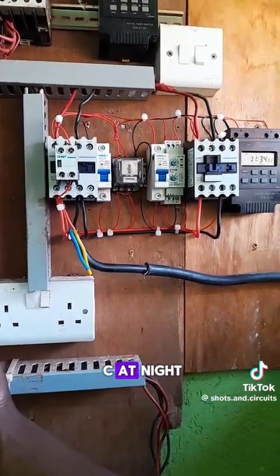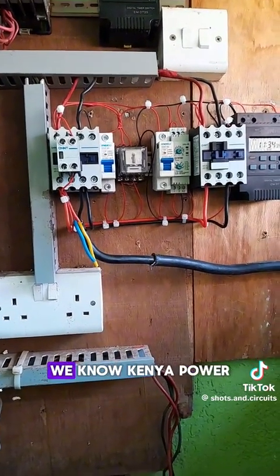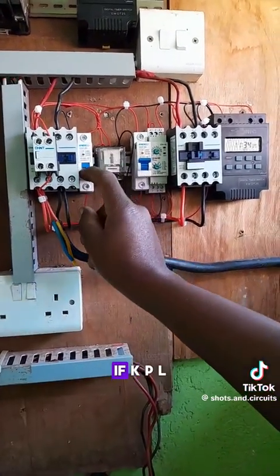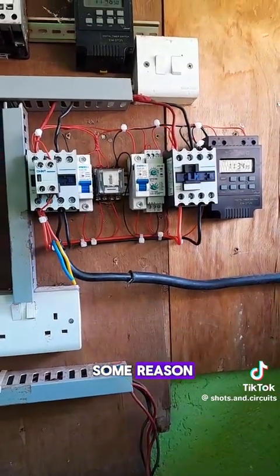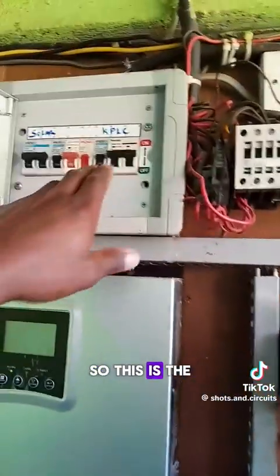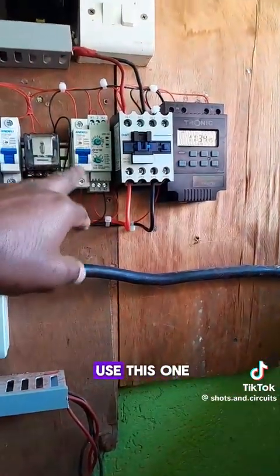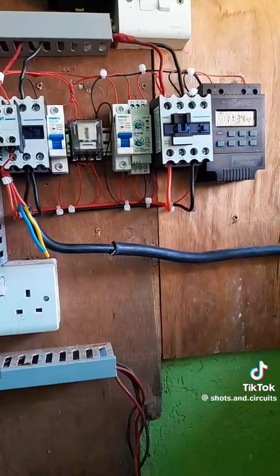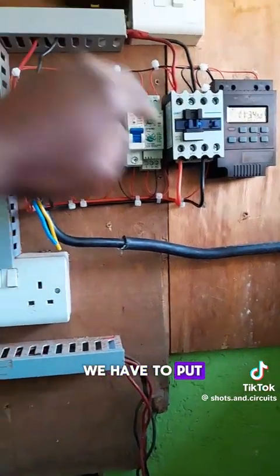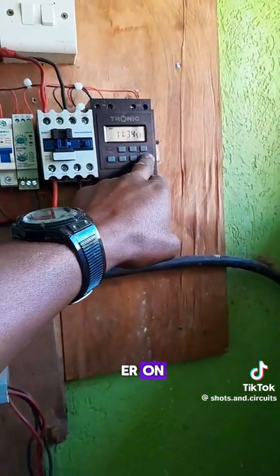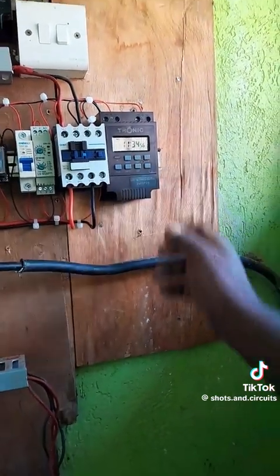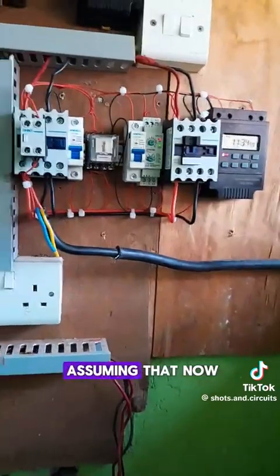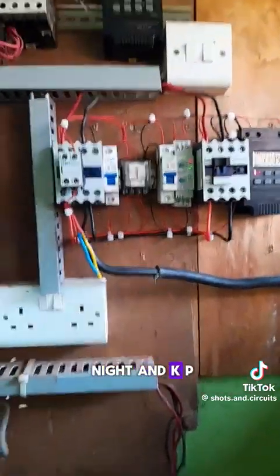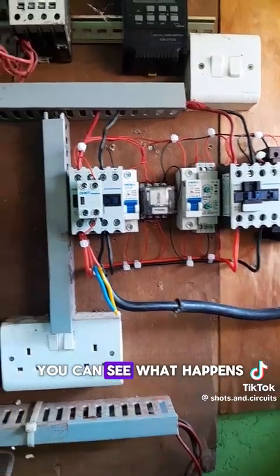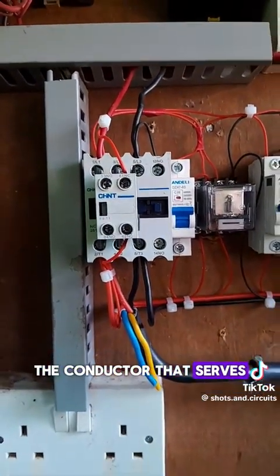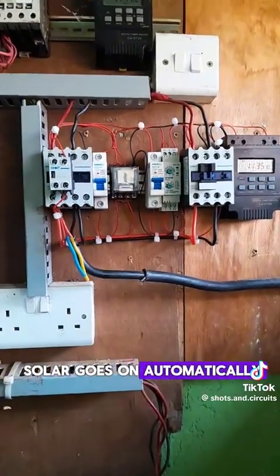If KPLC at night for some reason, we know Kenya Power and their problems, if KPLC at night for some reason depletes or the lights go off, so this is the double pole that controls KPLC, or also I can use this one. What will happen? First of all, we have to put the timer on, so that now, assuming we are using KPLC at night and KPLC goes off, you can see what happens. The contactor that serves solar goes on automatically.